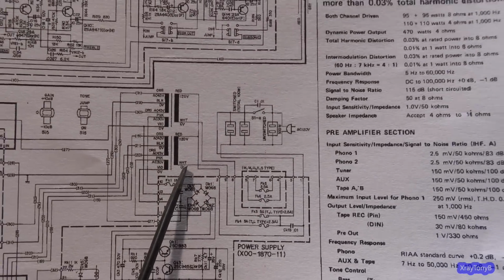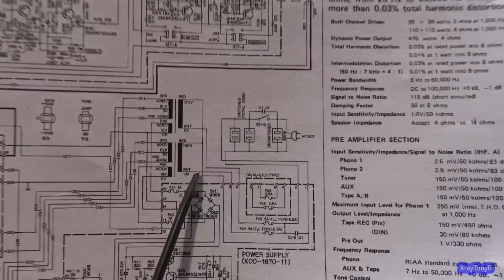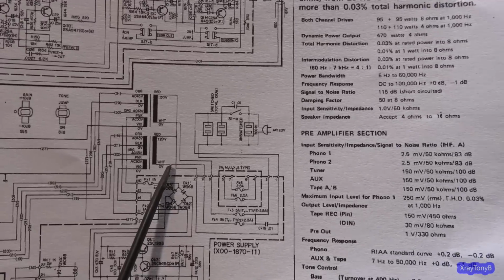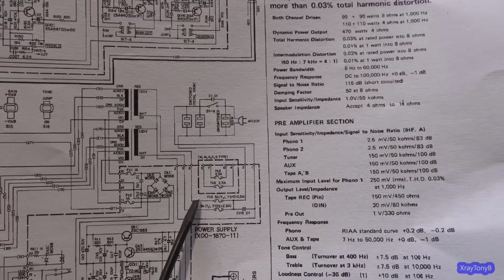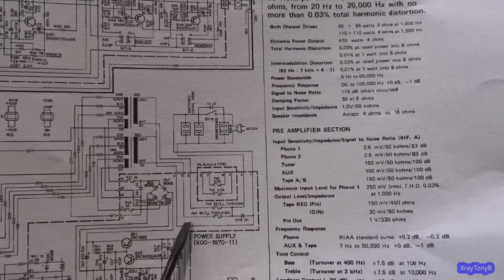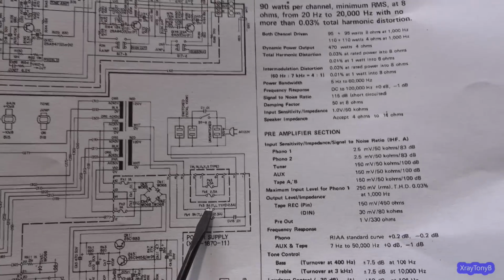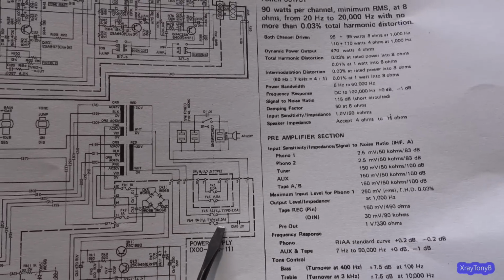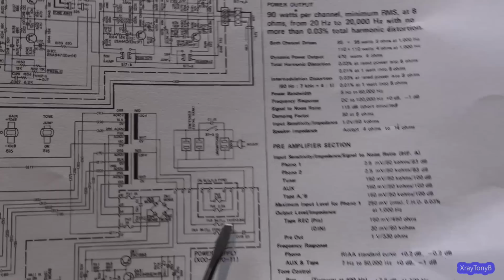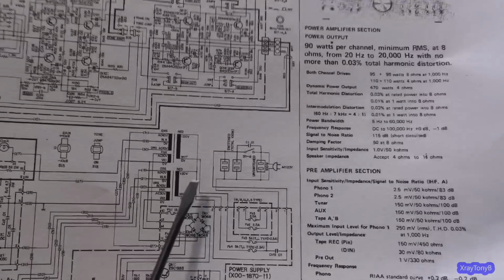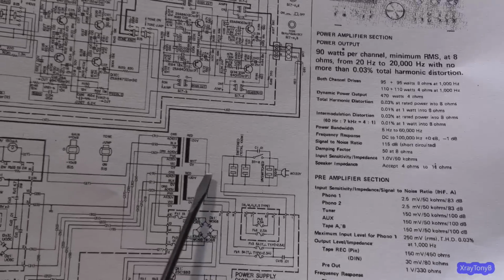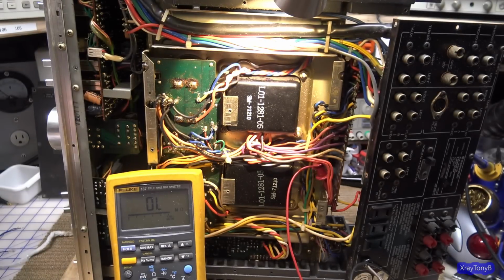White wires are separate though. They're not tied together between the two transformers. You have one of them going through one fuse and the other one going through the other fuse. So what I did was I popped these two fuses out, so now they're no longer tied together. That allows us to check across each coil, each transformer's primary individually.